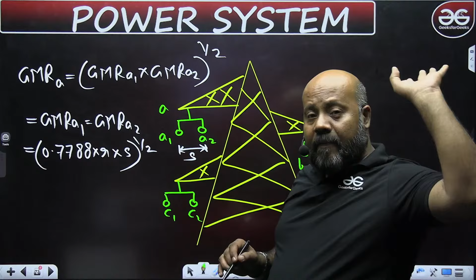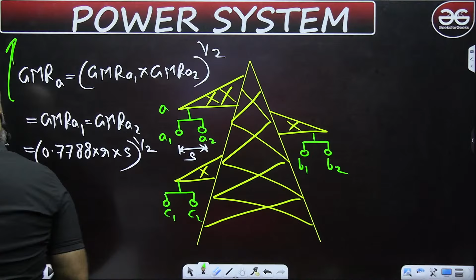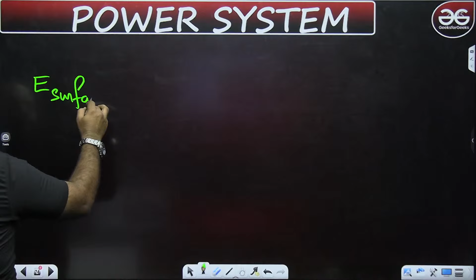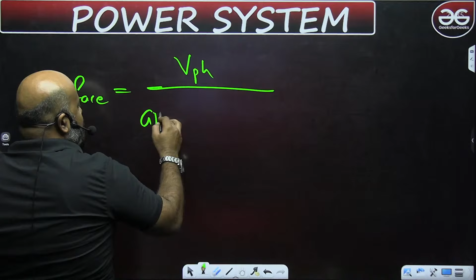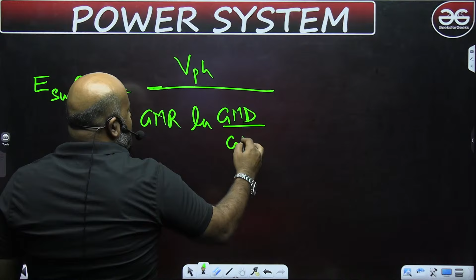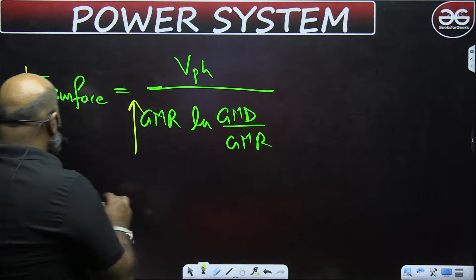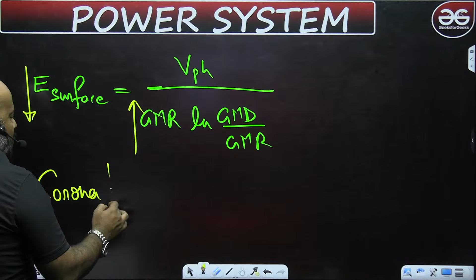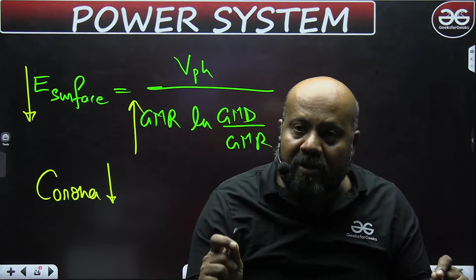Now by introducing this small distance S in case of bundled conductors, what have you done? By introducing S, you have increased the GMR. Sir, what happened by increasing the GMR? The electric field stress at the surface of the conductor is given as phase voltage divided by GMR, multiplied by ln of GMD upon GMR. If you increase the GMR, the electric field stress at the surface of the conductor is reduced. It means the possibility and intensity of corona is also reduced. So by introducing the bundled conductor system, you have overcome the problem of corona to some extent.